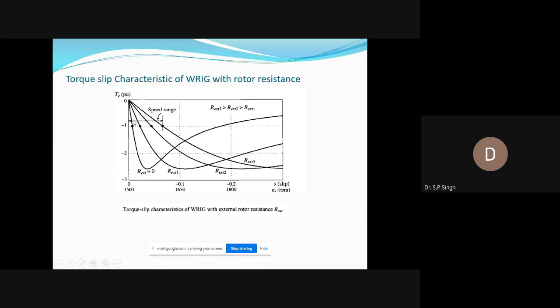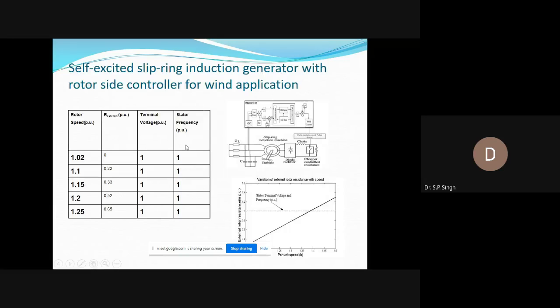So by increasing the resistance, you can change the torque-speed characteristic of a wound rotor induction generator. So you can understand how we can use a wound rotor, slip ring induction machine as a motor and as a generator.